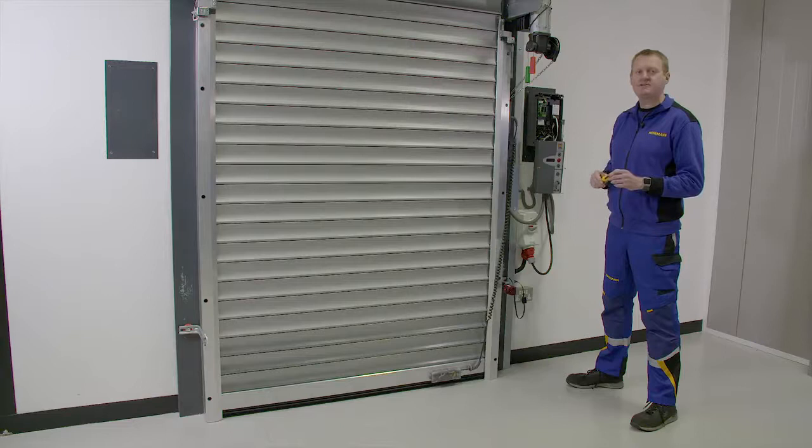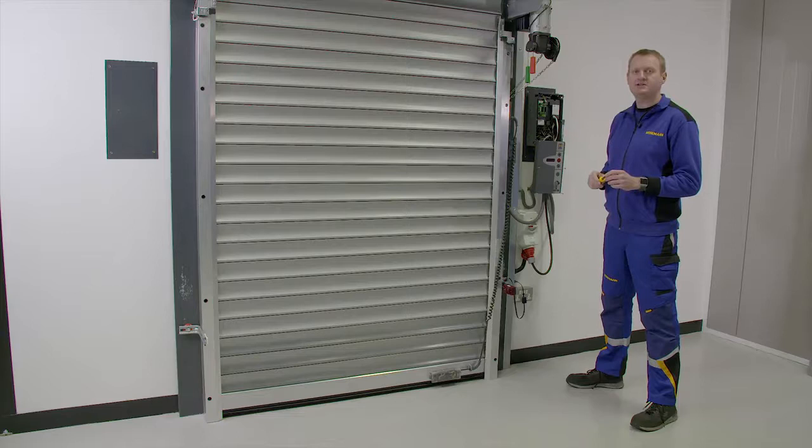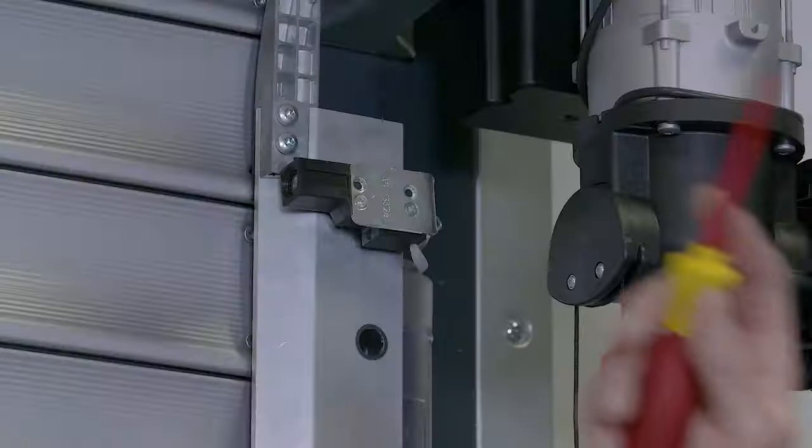This control panel looks for additional safety devices that should be fitted on certain doors. On roller shutters under two and a half meters high and on all roller grills, additional high level safety devices must be fitted.